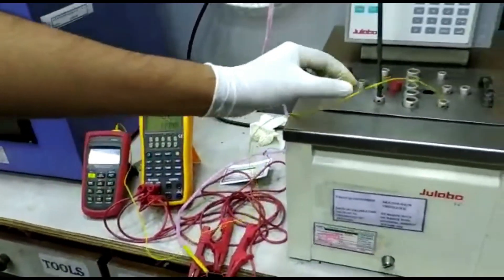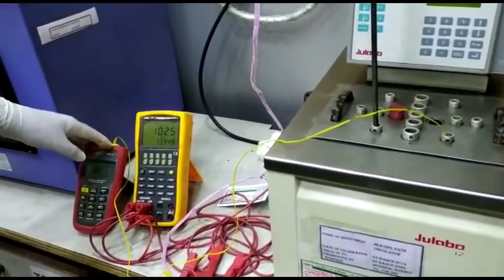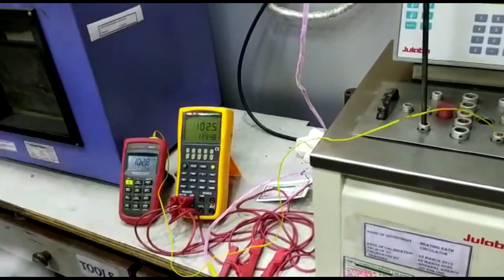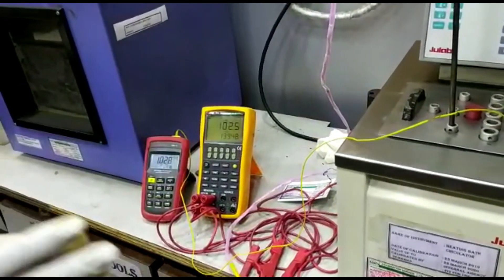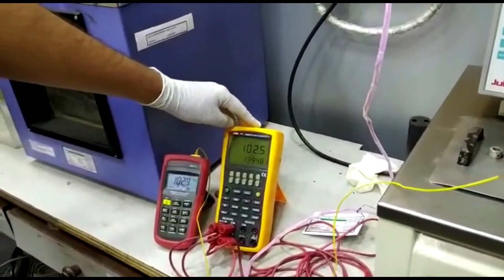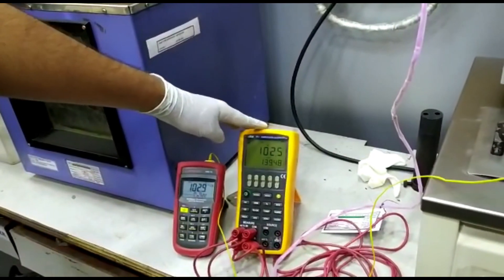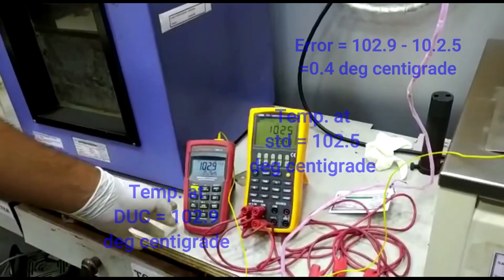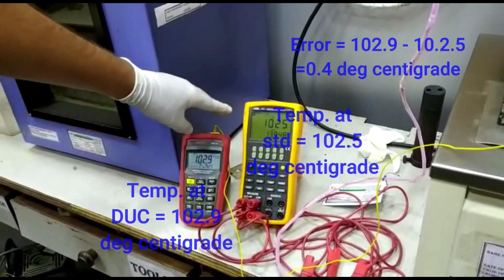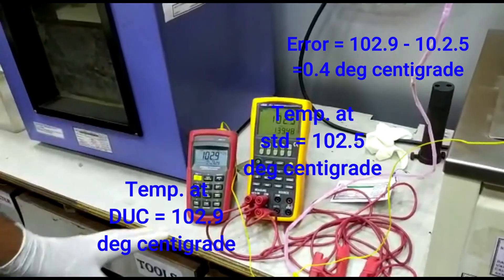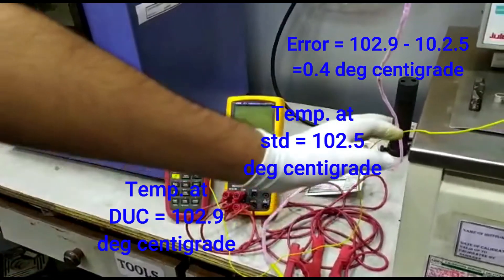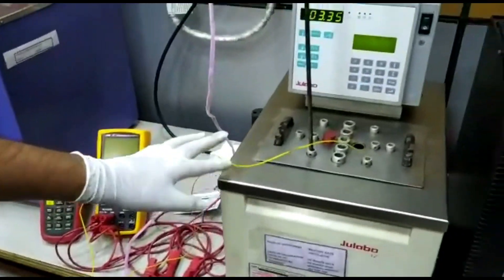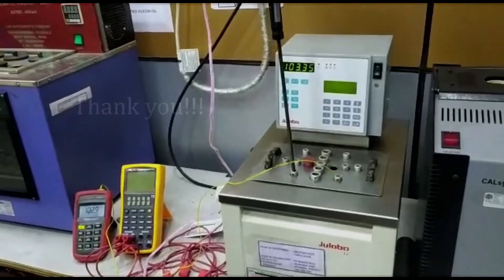DUC means device under calibration. We are calibrating this thermocouple by comparison method. That means we compare the reading of our standard and this DUC to get the error and we are getting the error of 0.4 degree C. That's it. The calibration of thermocouple by using temperature bath and SPRT. Thank you.